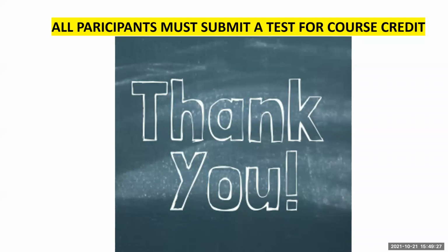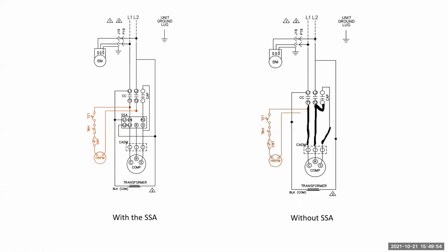The SSAs already come installed on the unit. You can't buy them anymore. They're obsolete. So you could put a hard start kit in place of one. You'd have to remove it totally and rewire the system, which is what that diagram was. Right here, we have the SSA that's wired in from the factory. Because they're no longer available, this is how you would remove it, and this is how you would wire in your compressor. I know it's kind of sloppy, but I got the job done.